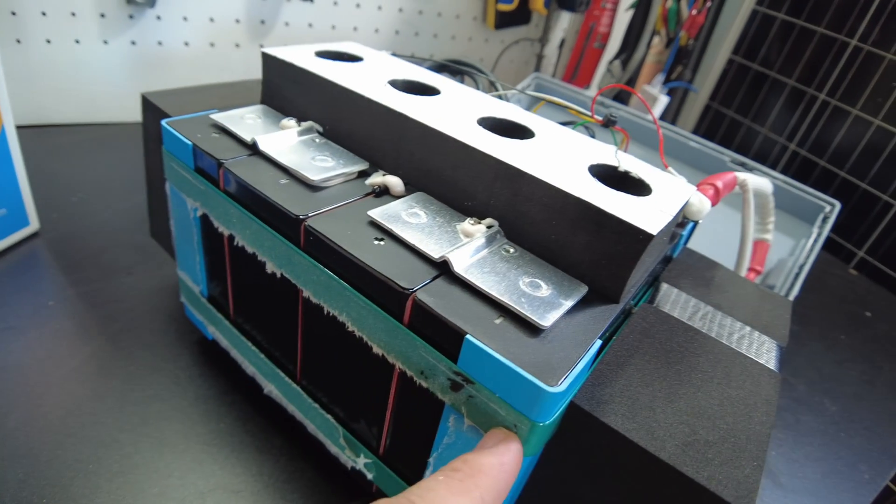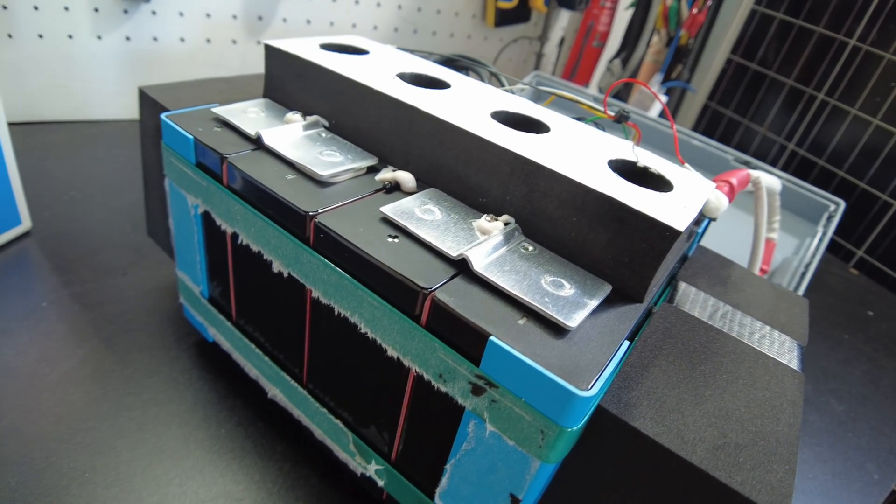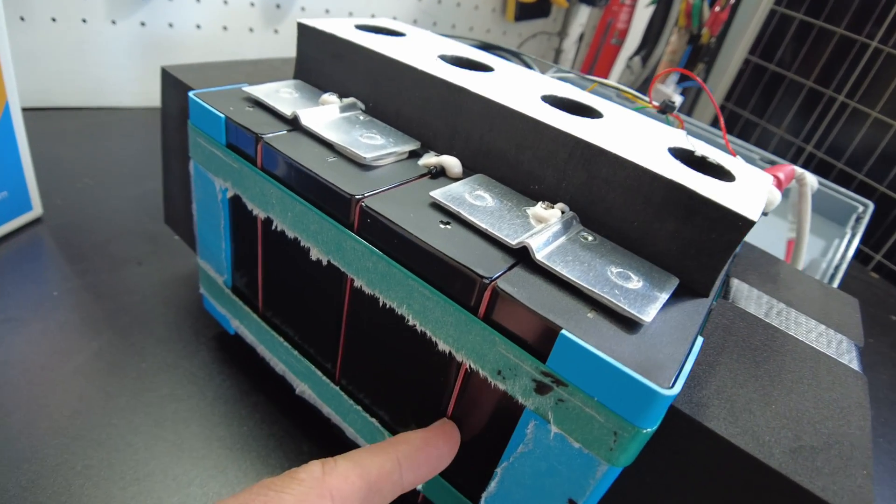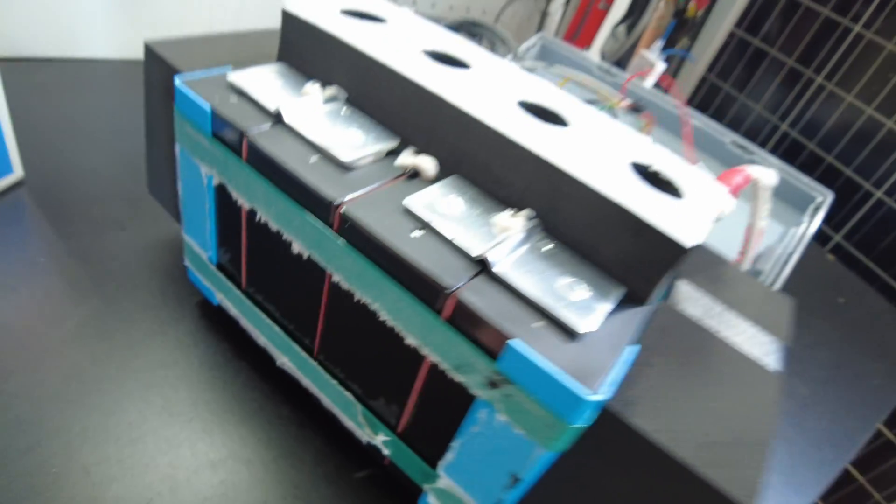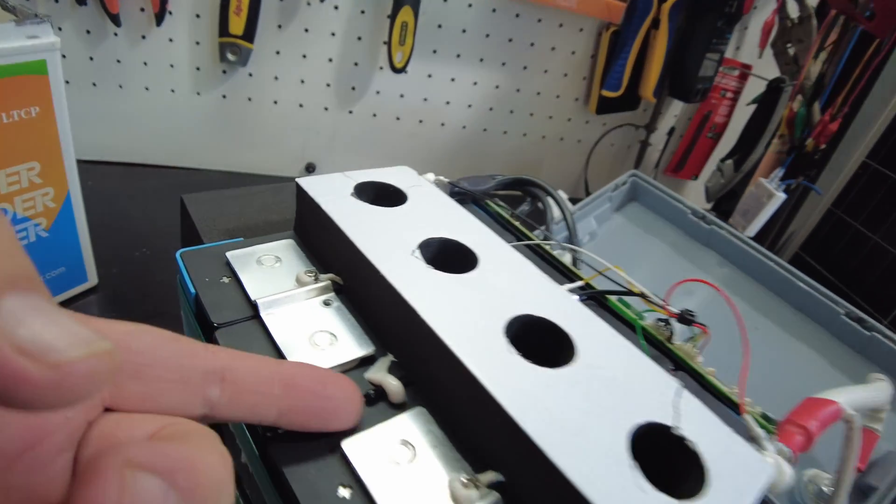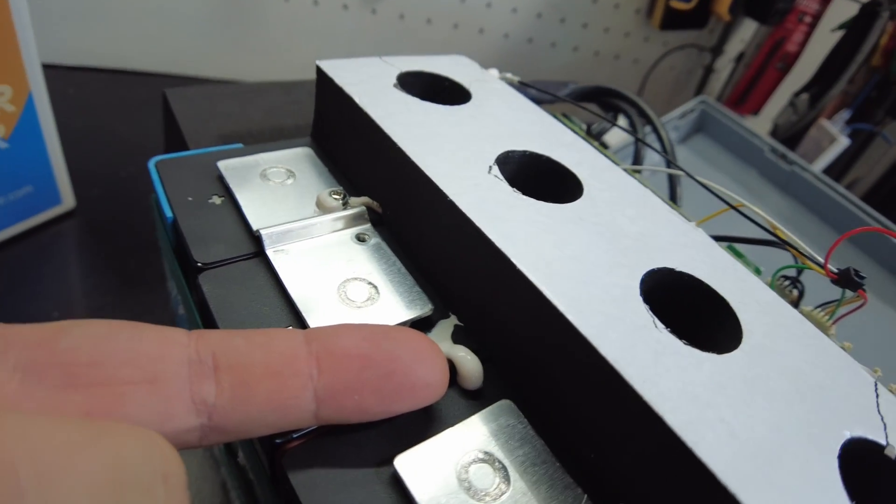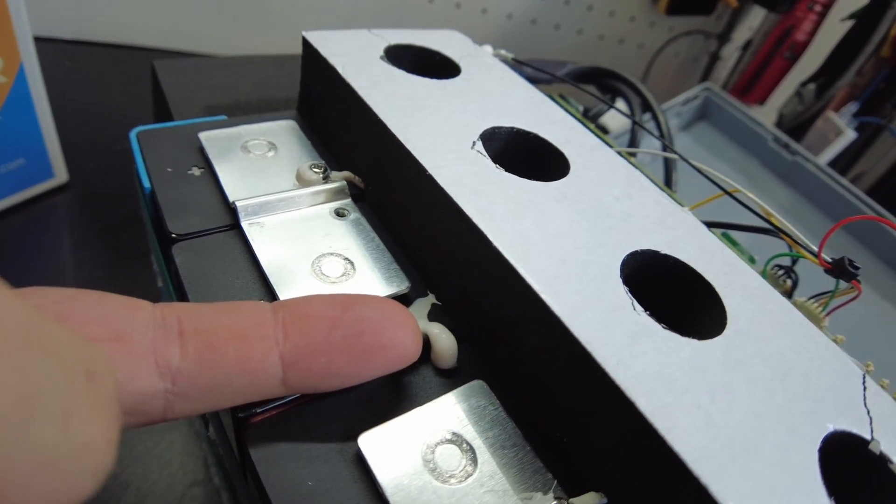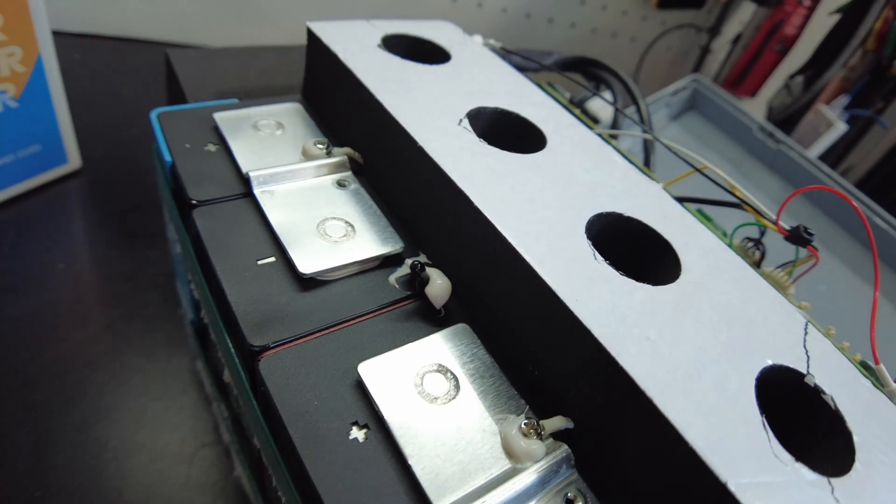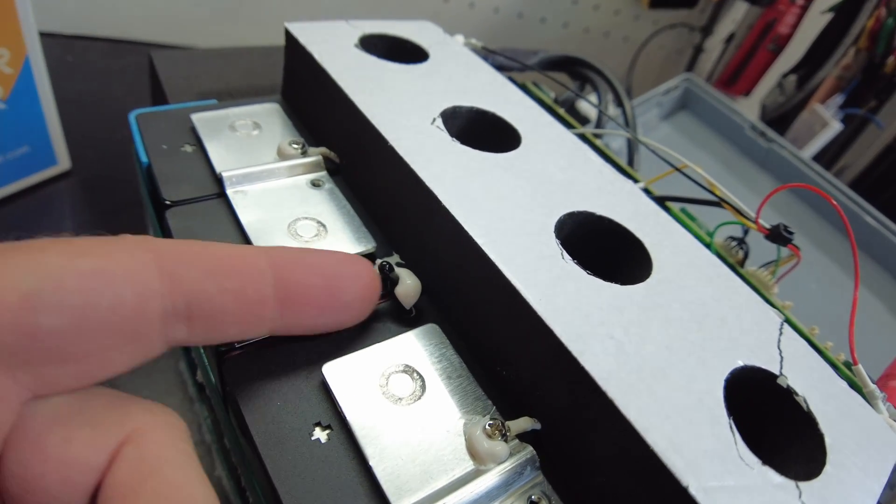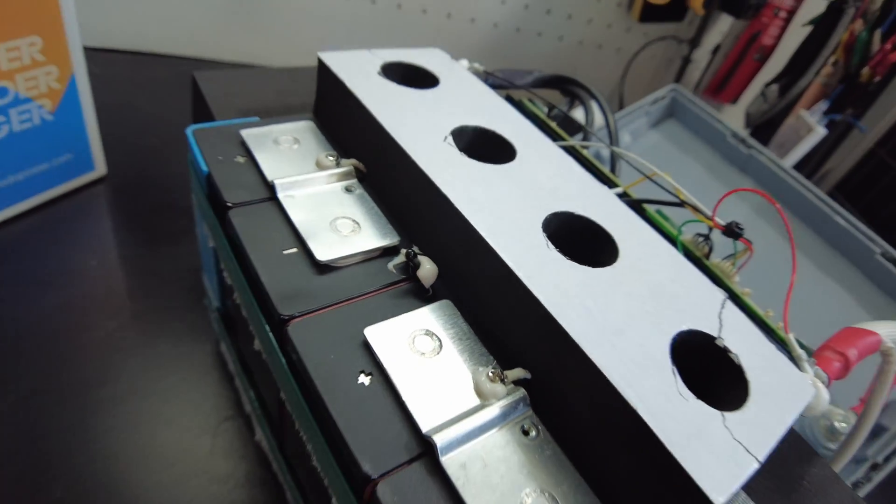The cells are banded together, got these plastic corners. Clearly again, they are prismatics. There is material between the cells to separate them. Fantastic. And I see a thermal sensor right here. So let's go ahead and try to test to see if we've got low temperature protection.